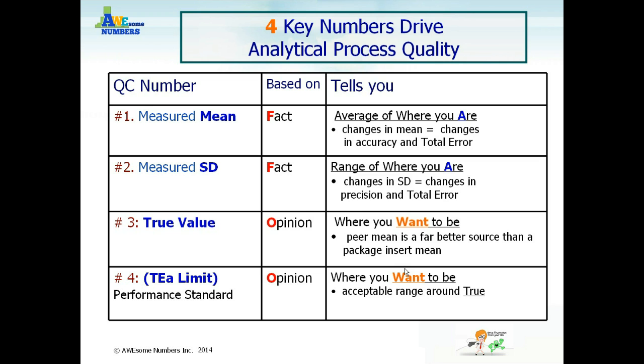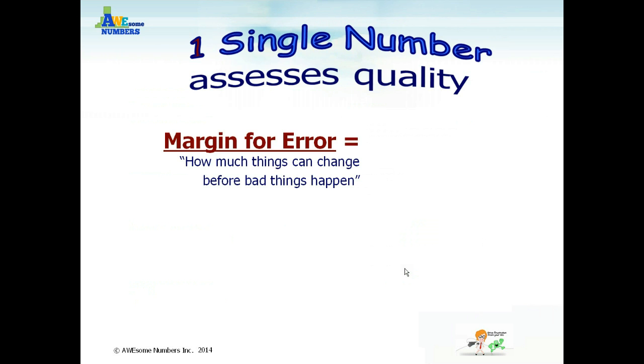You may choose biological variation, CLIA limits, clinically published limits, locally assigned limits.